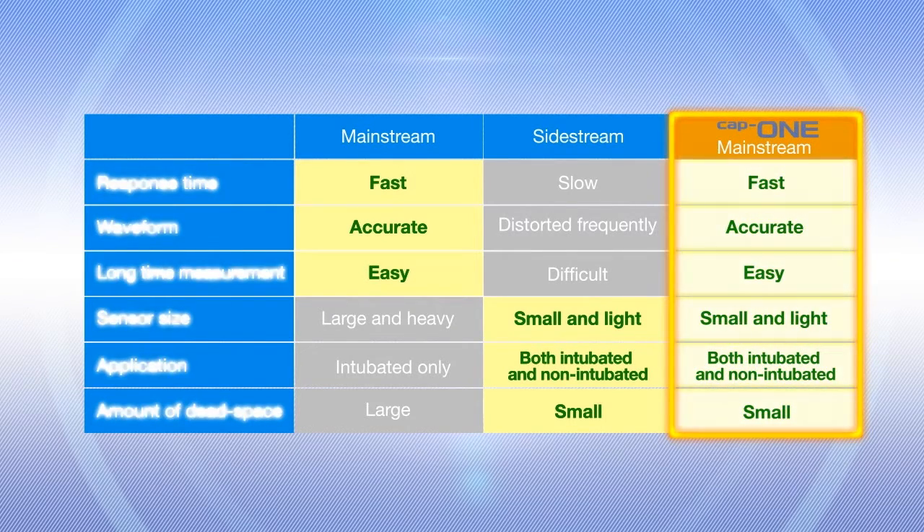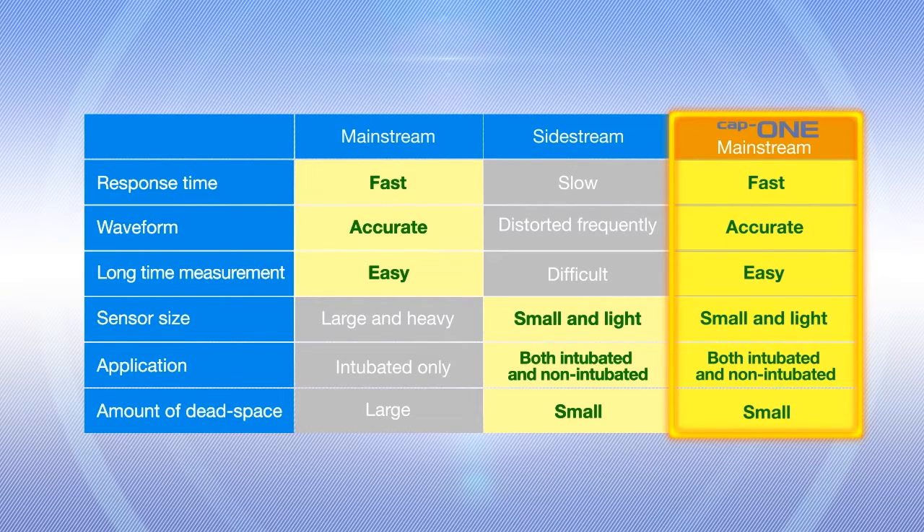Advantages of mainstream sensors are rapid response, less waveform distortion and few measurement interruptions. But compared to sidestream sensors, mainstream sensors are heavier, limited to intubated patients and have larger dead space. Now cap-ONE has overcome these disadvantages and maintains all the advantages of the mainstream sensor for optimal capnography.